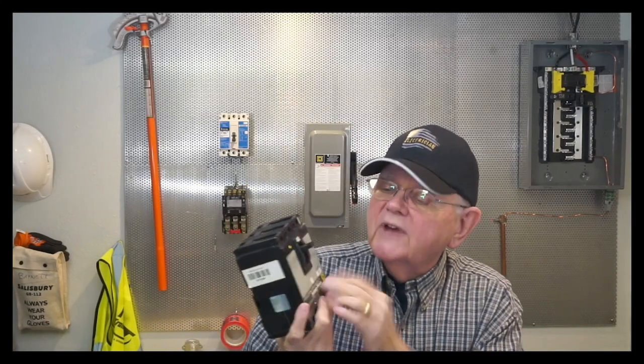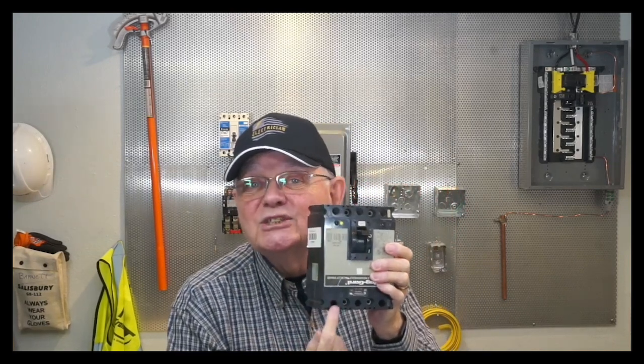We have other types of circuit breakers. For instance, this is an instantaneous circuit breaker. It has no inverse time feature to it at all. It builds up to a certain value and boom, the breaker trips. And that's it. So we use this breaker for short circuit and ground fault protection. In fact, in many applications, we'll talk about it up here on the board behind me in a minute, about what a motor controller is and a combination starter. But this particular breaker only has instantaneous trip, but the instantaneous trip is adjustable on this one.